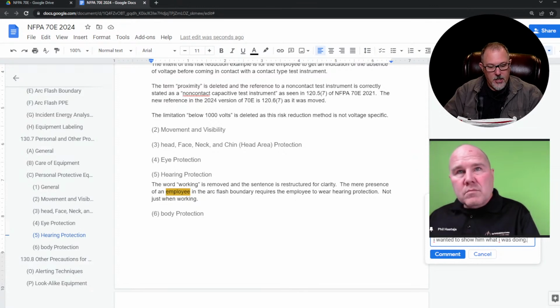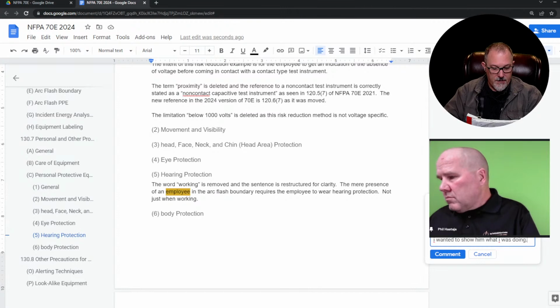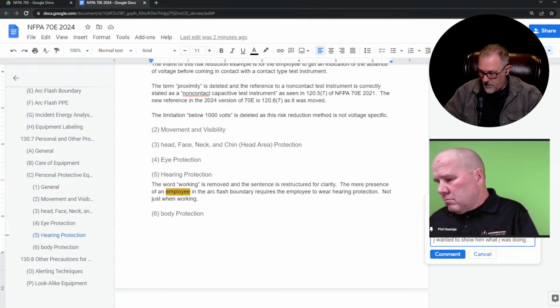It says arc-rated clothing with arc rating equal to or greater than the estimated incident energy: arc-rated long sleeve shirts and pants, coveralls, face shield, balaclava, outer rainwear as needed, leather gloves, protectors, hard hat, safety glasses, hearing protection.